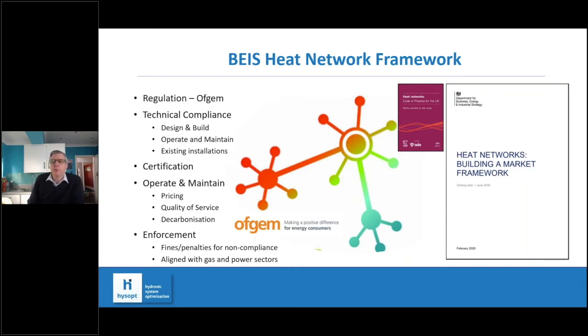the BEIS heat network framework, which essentially is going to bring regulation into the heat network sector. It's going to really require owners and heat suppliers to demonstrate compliance with technical standards, both for new and existing installations. Everything's going to have to be certified, so Ofgem will have to certify every scheme, and not only will new installations have to meet these technical standards, which will also include carbon compliance standards, but also on an ongoing basis, all of these heat networks will have to provide reporting and transparency around consumer pricing, quality of service, and how those systems are performing at a carbon level as well. So a lot more scrutiny and regulation coming into the market, and Ofgem will have the teeth to actually enforce this. A big change to the market that we know today.